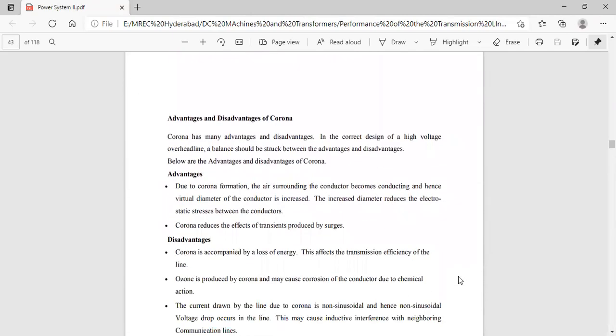The advantages and disadvantages of corona. Corona has many advantages and disadvantages. In the correct design of a high voltage overhead line, a balance should be struck between them. First, we'll see the advantages of corona. First point, due to corona formation, the air surrounding the conductor becomes conducting and hence the virtual diameter of the conductor is increased. The increased diameter reduces the electrostatic stress between the conductors. The second one is that corona reduces the effect of transients produced by surges.